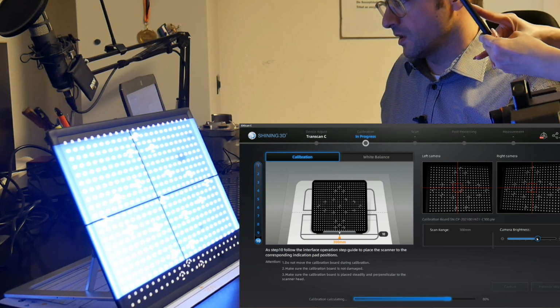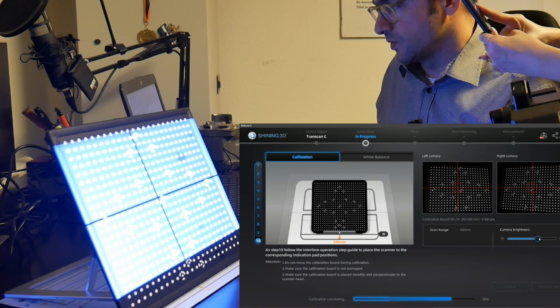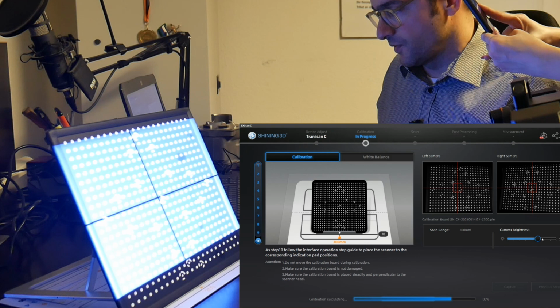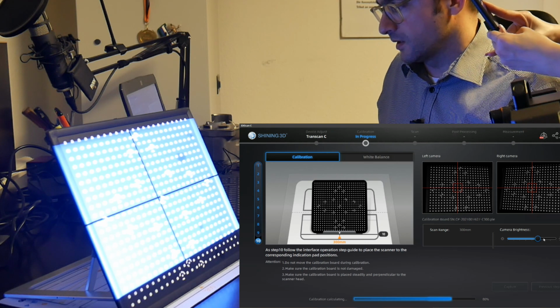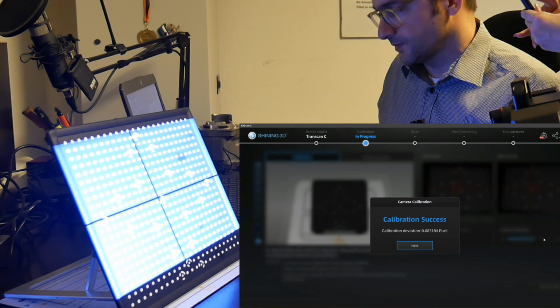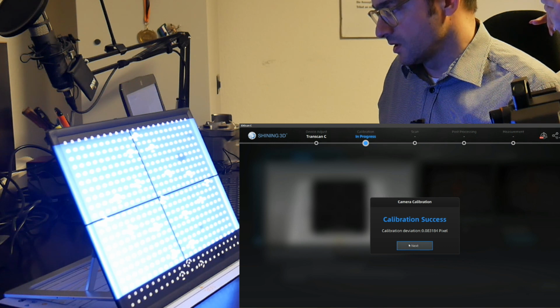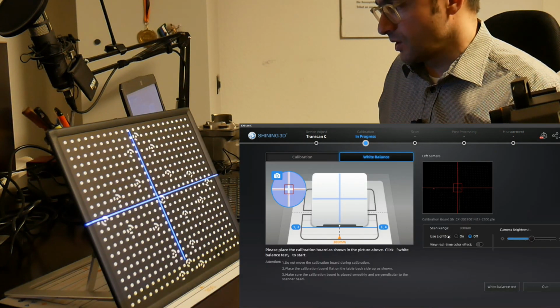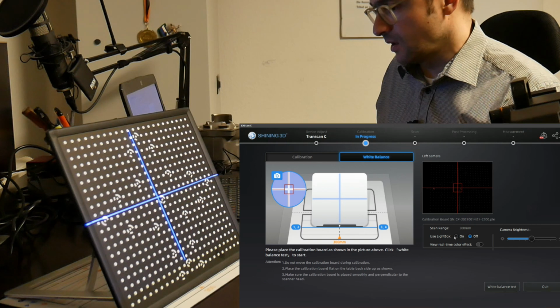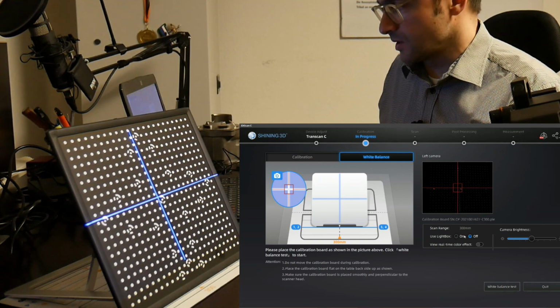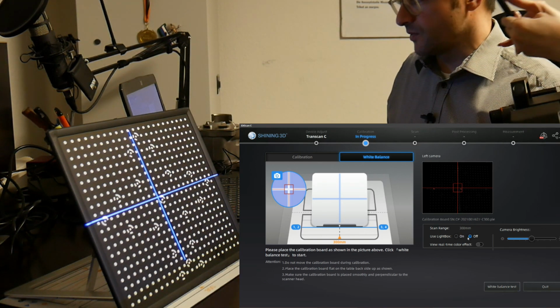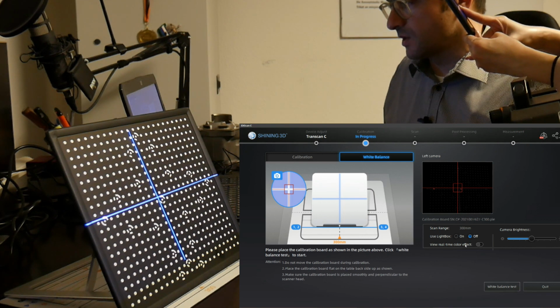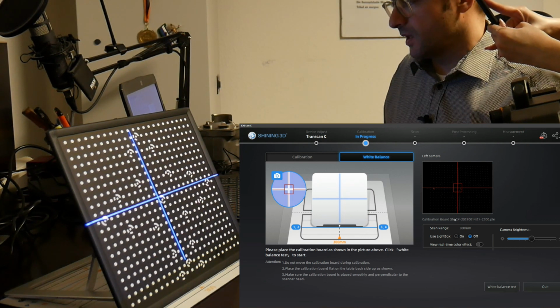Just to be sure, you've seen at the start that it was a bit too dark at the first distance, and after I raised the sensitivity, it was getting better. If you have a calibration that was done successfully, you will receive a message with the amount of pixels that you had as deviation.